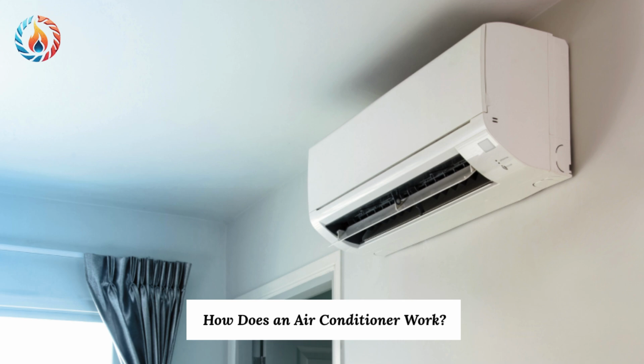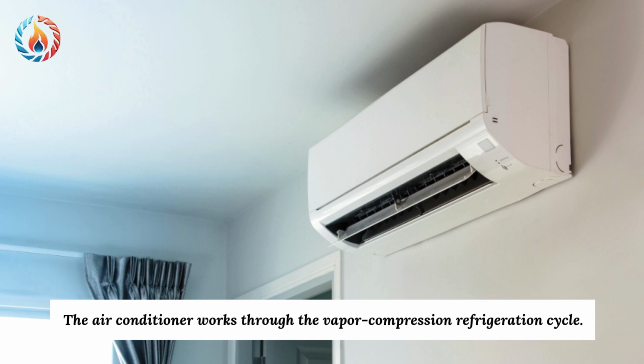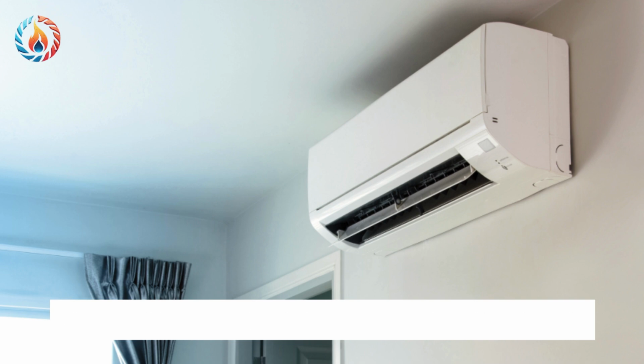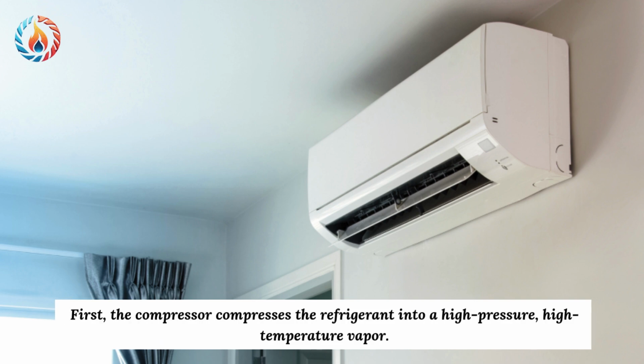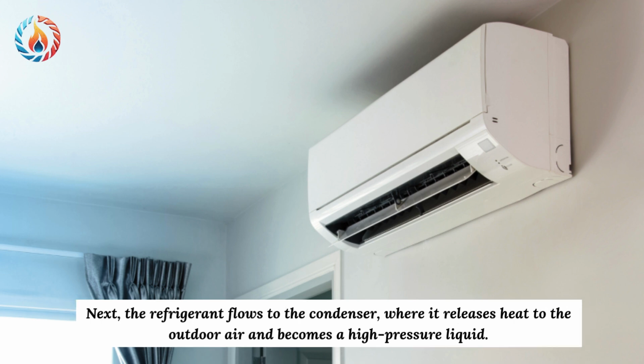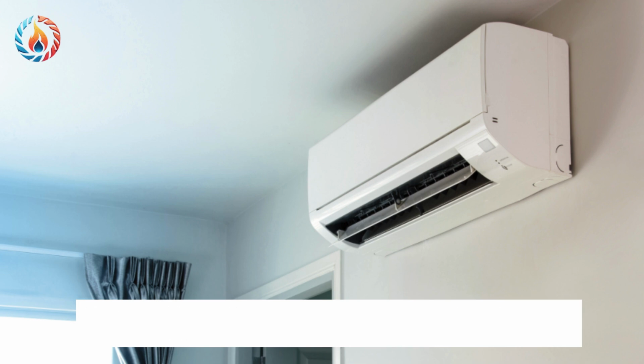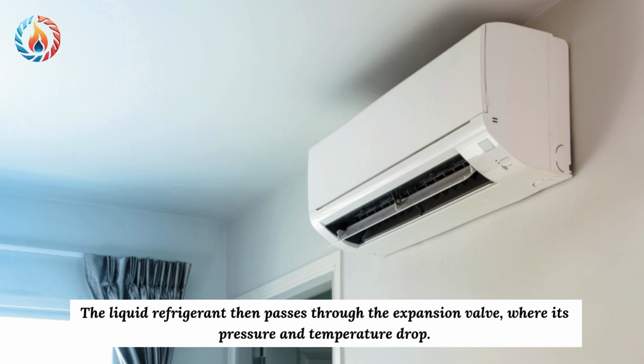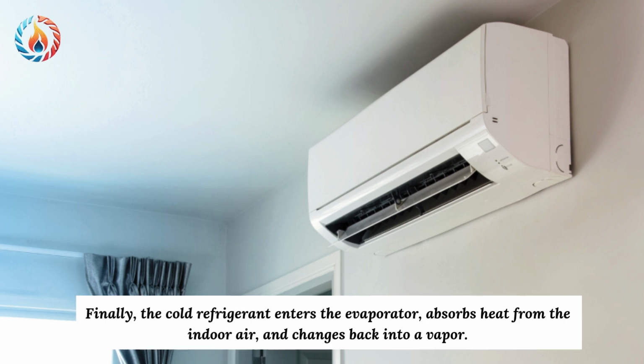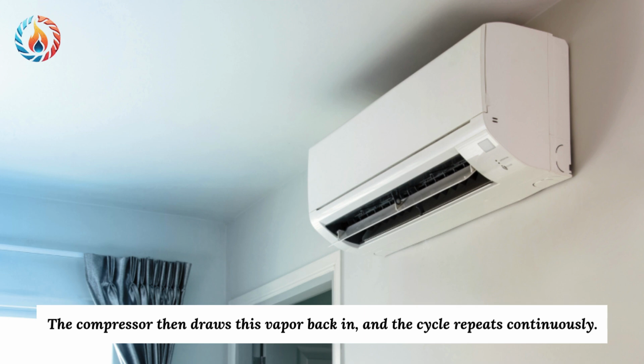How does an air conditioner work? The air conditioner works through the vapor compression refrigeration cycle. First, the compressor compresses the refrigerant into a high-pressure, high-temperature vapor. Next, the refrigerant flows to the condenser, where it releases heat to the outdoor air and becomes a high-pressure liquid. The liquid refrigerant then passes through the expansion valve, where its pressure and temperature drop. Finally, the cold refrigerant enters the evaporator, absorbs heat from the indoor air, and changes back into a vapor. The compressor then draws this vapor back in, and the cycle repeats continuously.